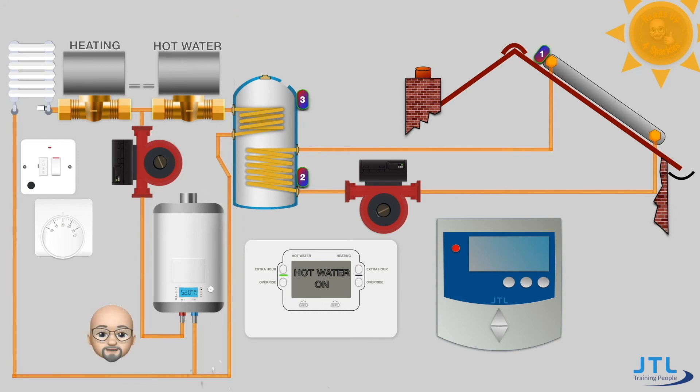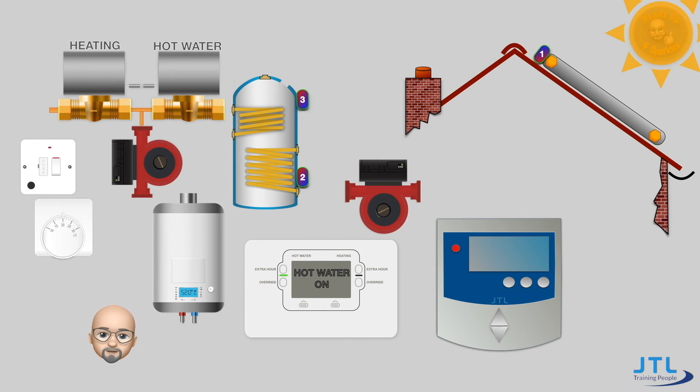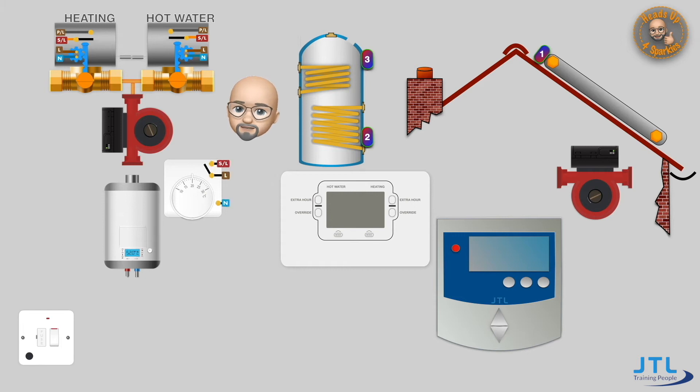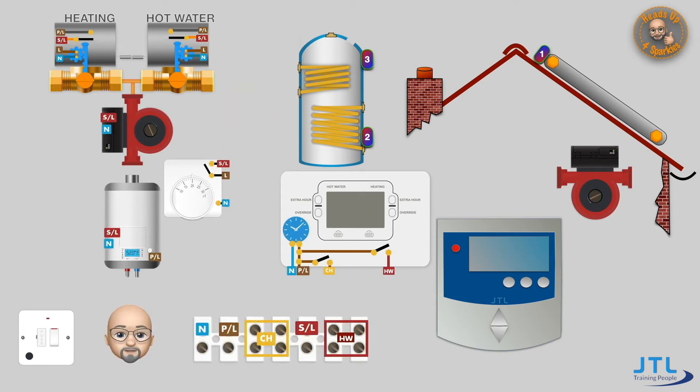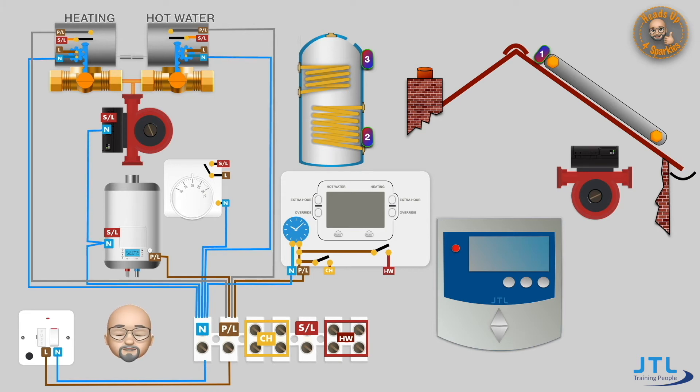Let's get rid of all the pipework and take a look at the wiring arrangements for this combined system. Firstly, let's quickly reconnect what remains of the S-plan system, retaining the wiring centre. Let's install the permanent lines and neutrals — CPCs have been excluded for clarity, but the system components' exposed conductive parts need to be earthed in line with BS 7671.